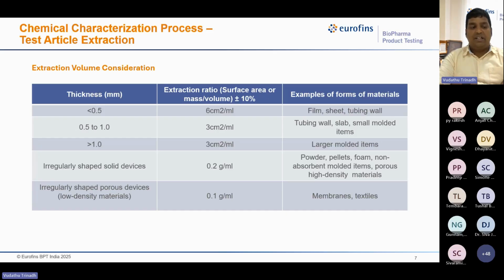Whereas, if the thickness of the medical device is 0.5 to 1 mm, then the extraction volume selection will be 3 cm² per ml. In this case, examples of materials are tubing wall, slab, and small molded items. If it is more than 1 mm thickness, those can also fall under the extraction volume of 3 cm² per ml, and examples for this are larger molded items. Whereas when the surface area is irregular and cannot be calculated, the extraction volume can be selected based on the weight of the medical device, like 0.2 gram per ml as the ideal case.